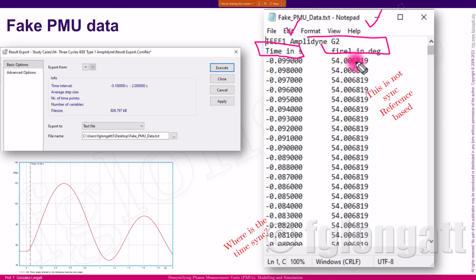However, this is what I call fake PMU data, because there is no synchronization here. There's one very important property of PMU data missing, and that is the wrap angle. In a minute I'll explain what the wrap angle is, but what you're seeing here is a phase angle coming from an offline simulation, which will never be identical to a data stream coming from a phasor measurement unit.